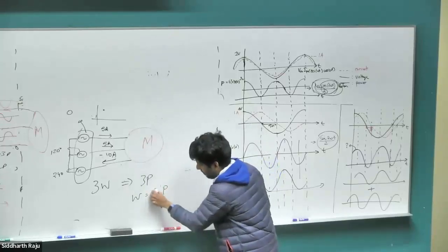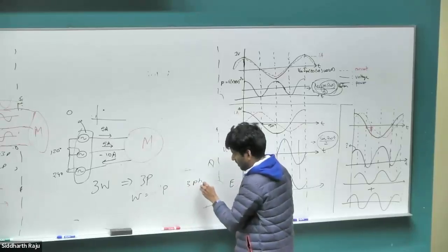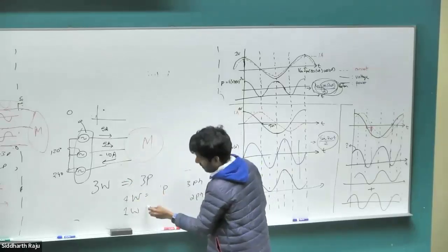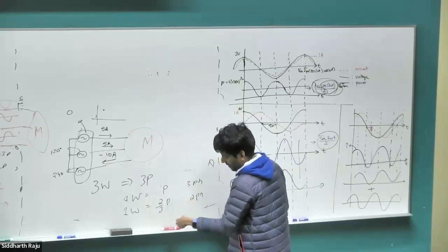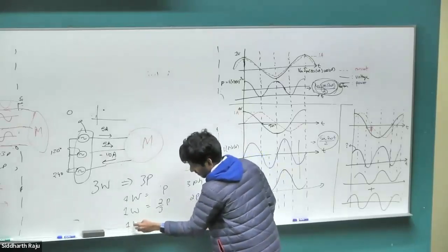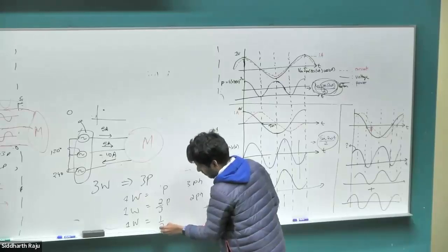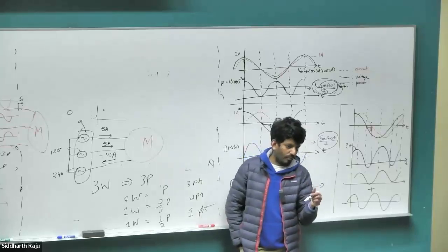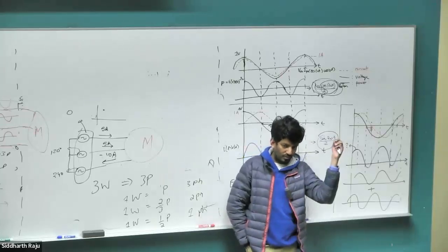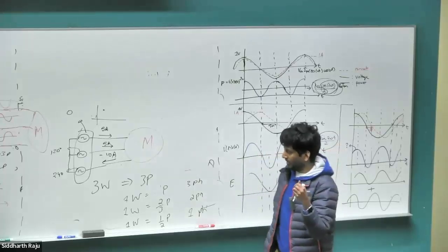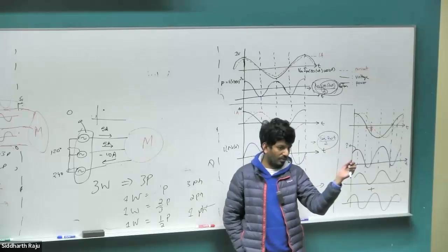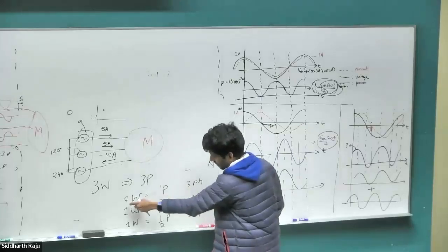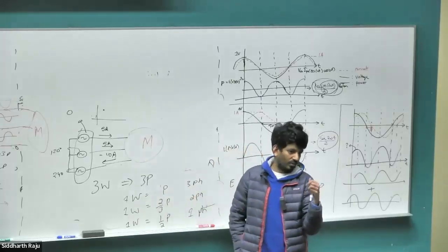Right? So each wire in this case carries power P in the three phase case. In the two phase case, each wire carries the power 2 by 3. In the one phase case, each wire carries half P. Right? So for given copper wires, these transmission wires are running across the country. They're quite expensive. So you want to optimize how much power you can transfer for the amount of copper you lay out, right? Or aluminum wires that you lay out, typically aluminum strands. So the three-phase system gives you the maximum amount of power per wire that you put in your infrastructure.